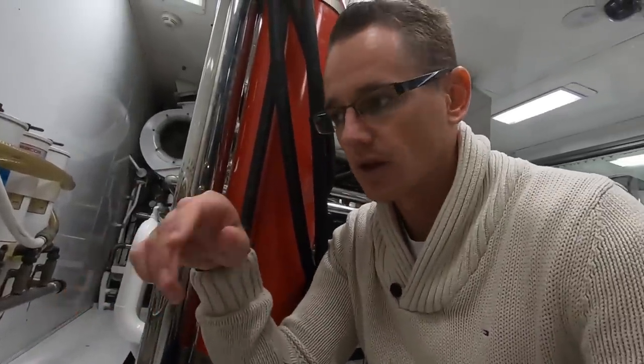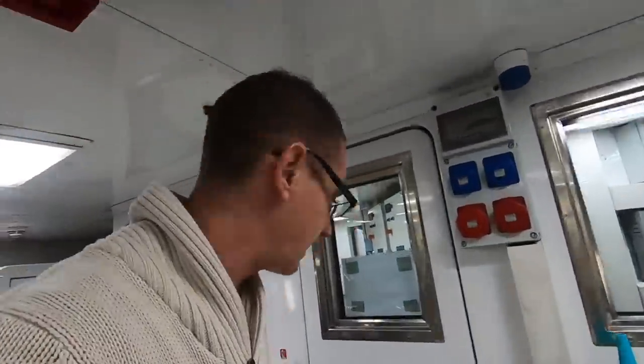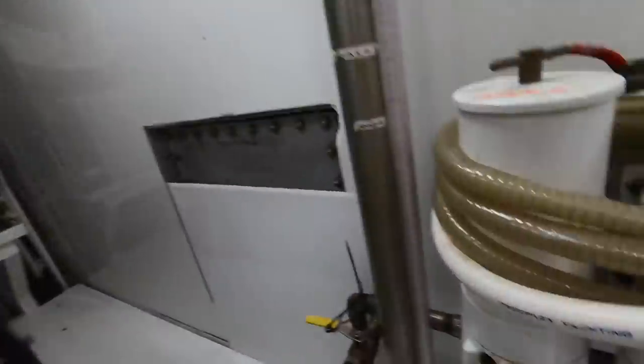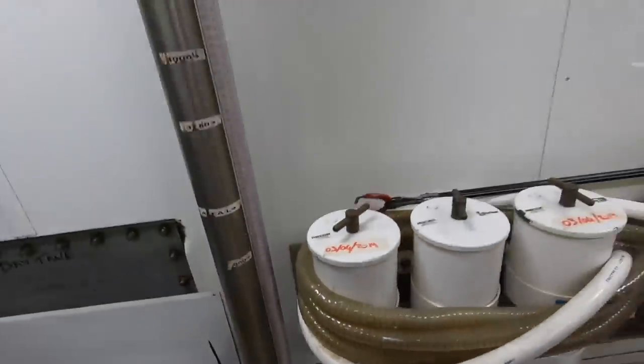Further down we have four emergency fuel shutoff valves. In the event of a fire in the engine room, if we can't get inside, we want to isolate the fuel so it doesn't feed the fire. We exit the engine room and there's a lever handle just outside. By pumping it up and down, it triggers all four emergency shutoff valves to engage simultaneously, shutting down fuel supply to the engine room.